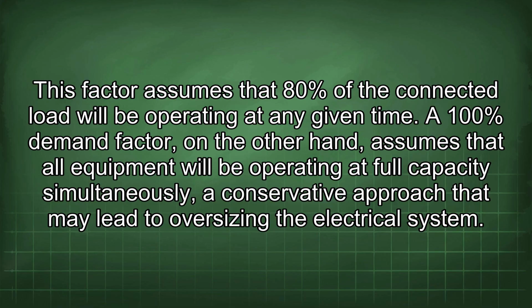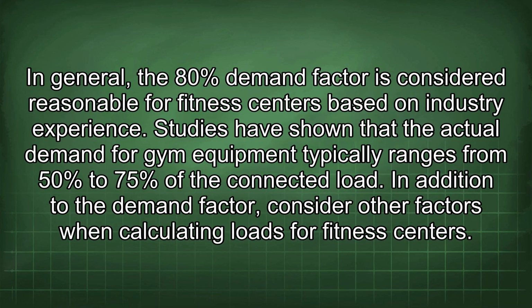A 100% demand factor, on the other hand, assumes that all equipment will be operating at full capacity simultaneously, a conservative approach that may lead to oversizing the electrical system. In general, the 80% demand factor is considered reasonable for fitness centers based on industry experience. Studies have shown that the actual demand for gym equipment typically ranges from 50% to 75% of the connected load.